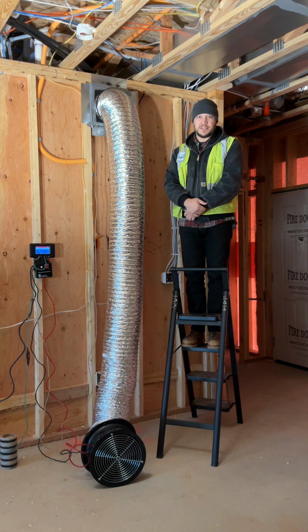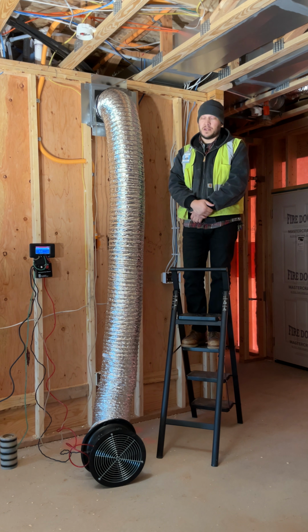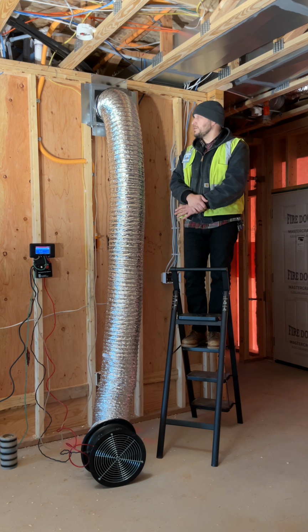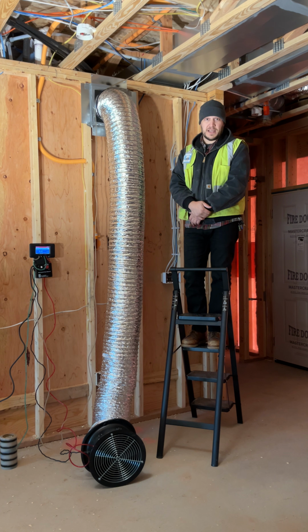Before the air handler is installed is a great time to do a rough-in duct leakage test. We're currently hooked up just to the supply side. We'll tape off all the other supplies and any other entry points into the system and measure the leakage, and that'll help find out where any leaks are early before drywall goes in. We'll also do the same thing on the return side, and that'll help us meet our leakage targets at the end of our project.